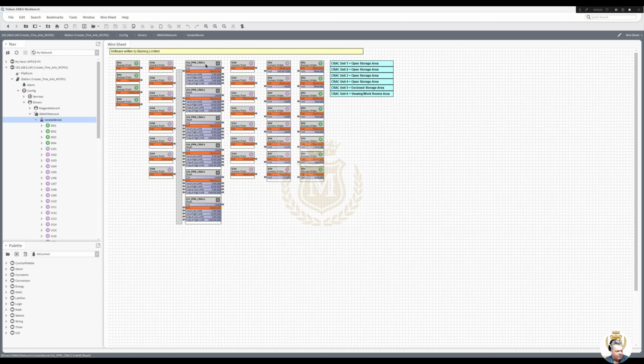Now with the CRAC units, we've got a parts per million sensor, ppm, for each CRAC unit. All I've done there is where I've got the input for it, in this case universal input 2, going into there, 0 to 10 volts, 0 to 1000 out. Now the reason I've done that instead of changing the point, because I could have just adjusted this point, and I can just adjust the scale to go 0 to 1000.